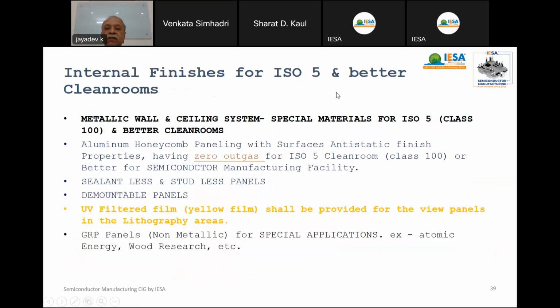But for internal finishes for ISO 5, class 100 clean room, it requires a special material. Okay? Metallic wall and ceiling system, a special material for ISO 5 and better, is aluminum honeycomb paneling with surface anti-static finish. So anti-static finish is more important. Even from the wall panel, you cannot expect contaminants in static charges. So the surface finish of the wall panel and ceiling panel will be anti-static. Apart from that, we have zero outgassing rate. Zero outgassing rate means the number of particles in micrograms per second per square centimeter. In the sense, so many micrograms of particles from 1 square centimeter of surface area in 1 second should be as low as possible. Normally, we have to go for a zero outgassing rate for ISO 5, class 100.